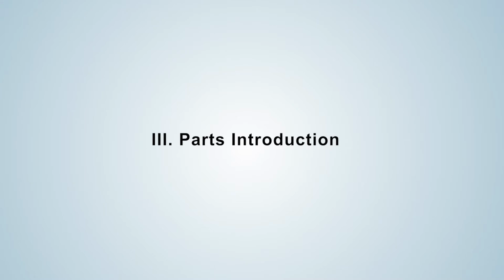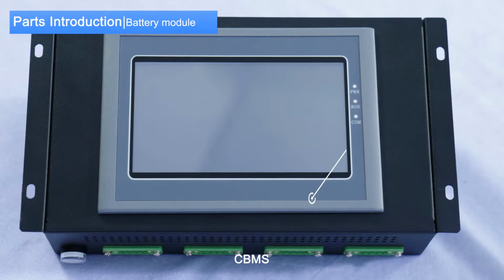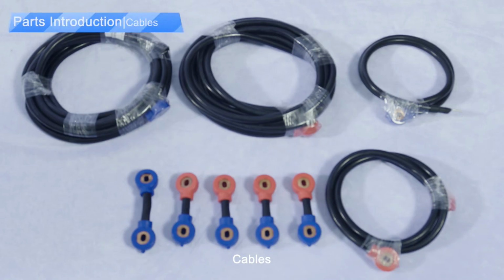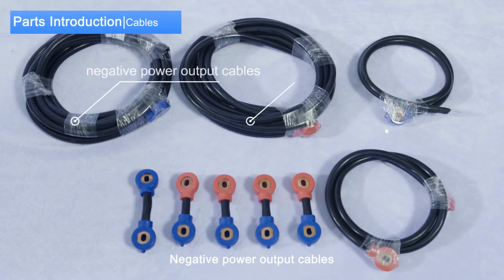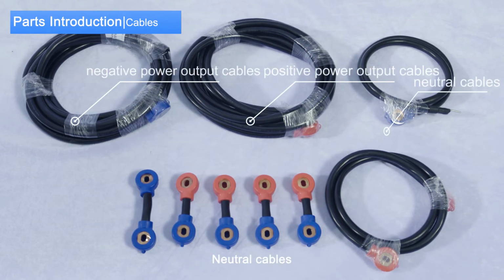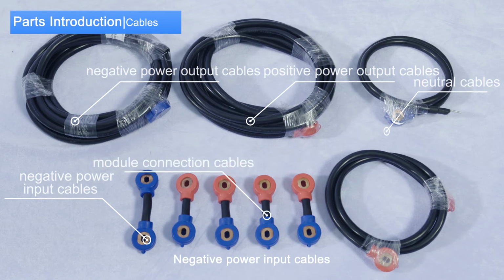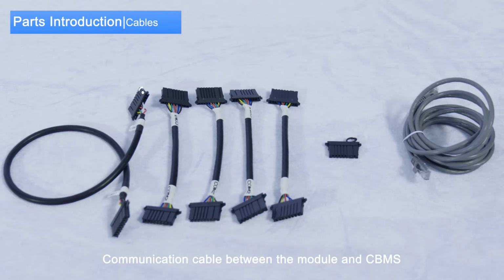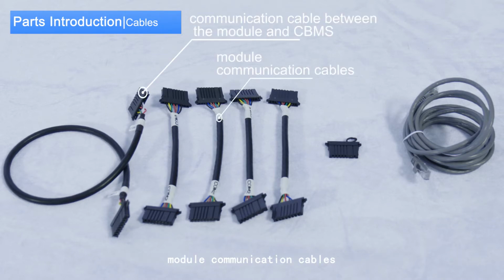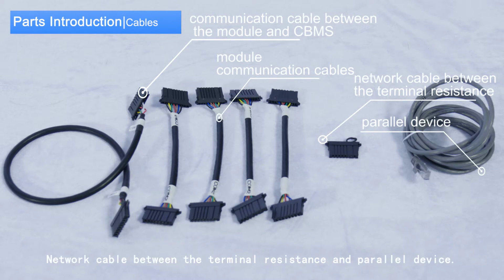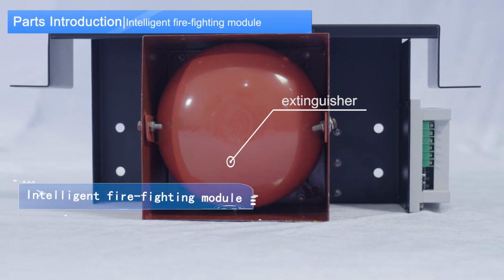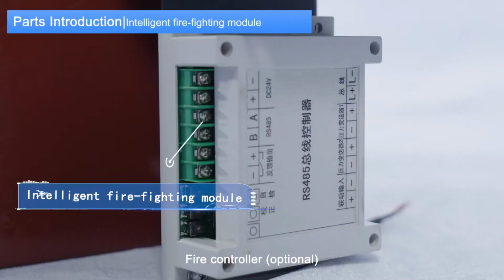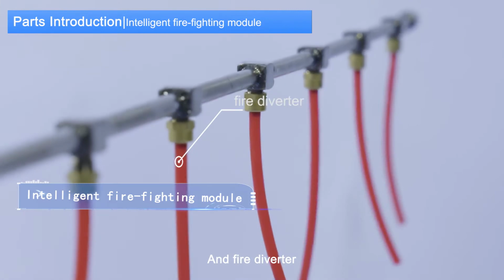3. Part introduction. Please prepare these parts: battery module, CBMS, GBMS, cables, negative power output cables, positive power output cables, neutral cables, negative power input cables, module connection cables, positive power input cables, communication cables between the module and CBMS, module communication cables, network cable between the terminal resistance and parallel device. Intelligent firefighting module, extinguisher, fire controller, optional, and fire diverter.